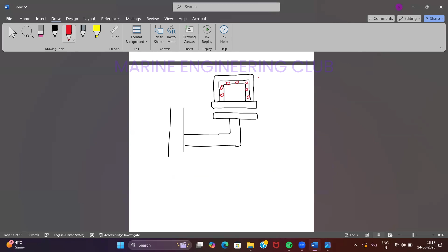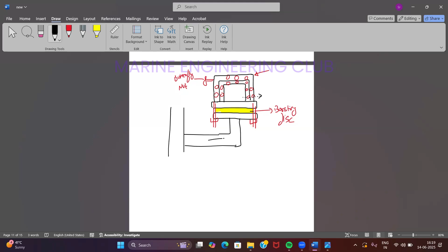Okay, now this is your bursting disc here, yellow color. This thing will be connected by nuts and bolts, these flanges, and you have one butterfly nut over here. So in normal operation, these holes are aligned together. Okay, you can see right now it is aligned together. So if, for example, any condition arises that your bursting disc bursts out, whatever pressure will be coming out due to the bursting disc having burst can go out from these holes.